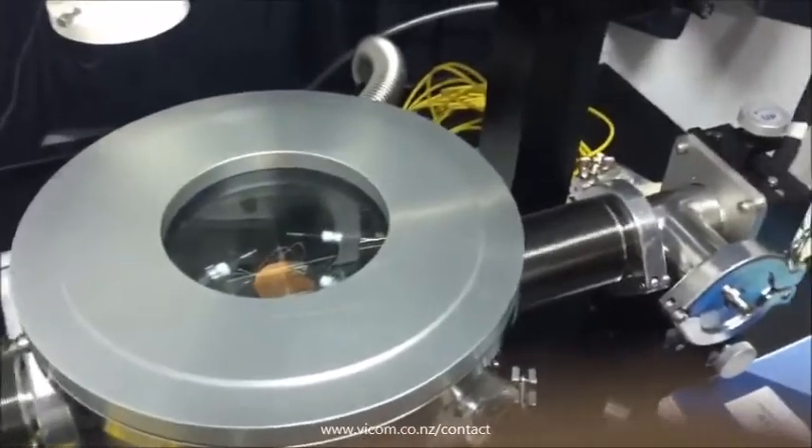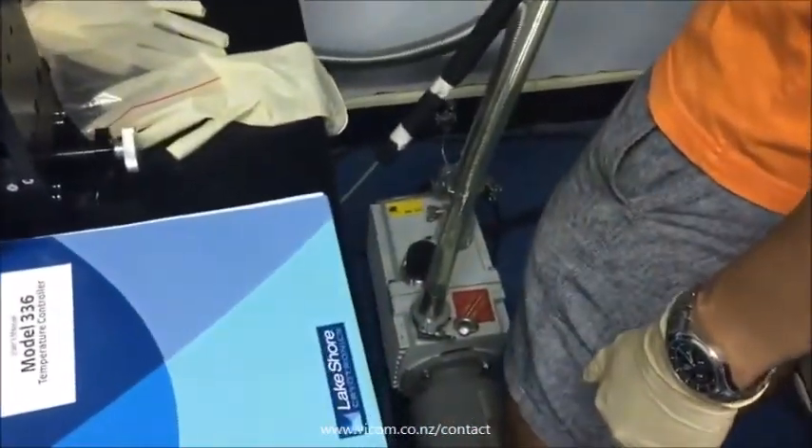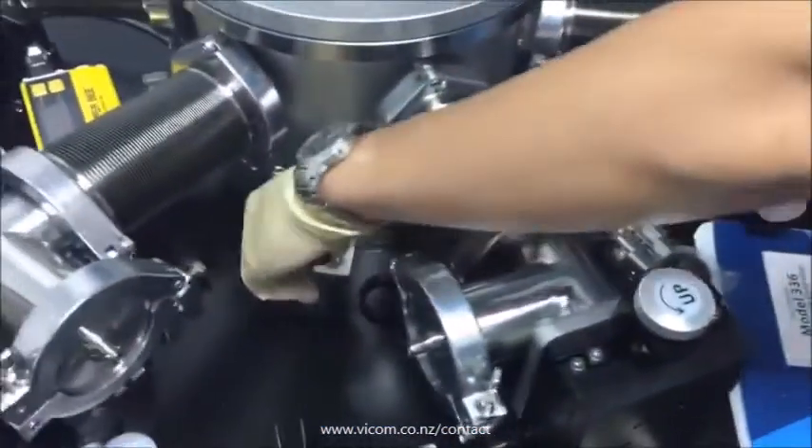Step 3: Turn on the vacuum pump and the vacuum gauge. Check the screen of the vacuum gauge — the reading should reach around 190 mTorr — then open the vacuum isolation valve.